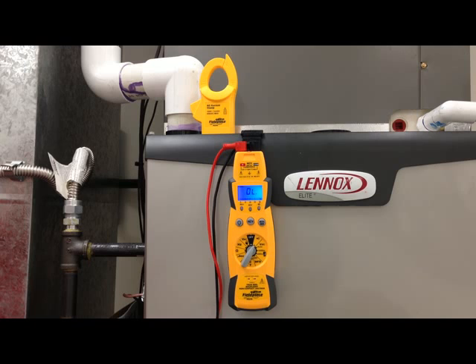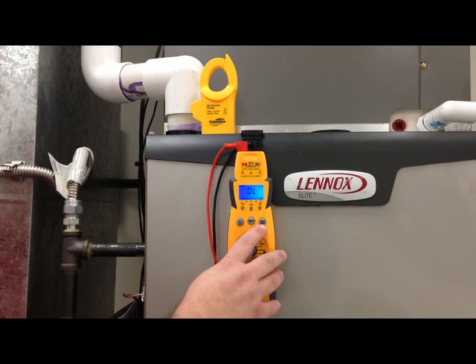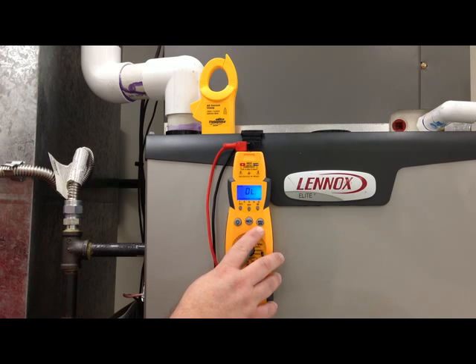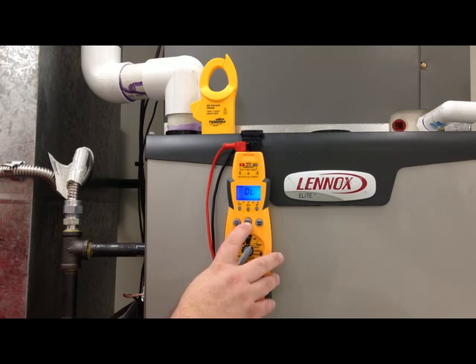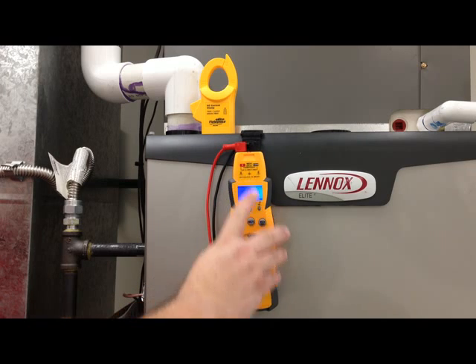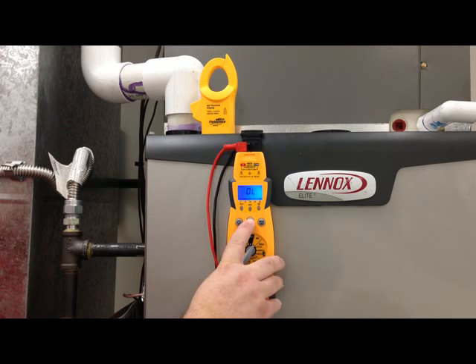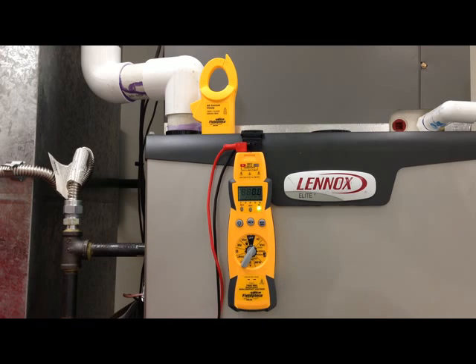A couple other things you really need to spend the time to notice about your meter are some of the other buttons and features it may have. For example, the min-max scale to capture the highest and lowest values of whatever you're reading. And on this meter, the NCV stands for non-contact voltage. If I take the top of the meter and dangle it in front of a wire and press down, it'll emit a buzz to let me know if that wire has voltage. The louder the buzz is, the higher the voltage of the circuit.